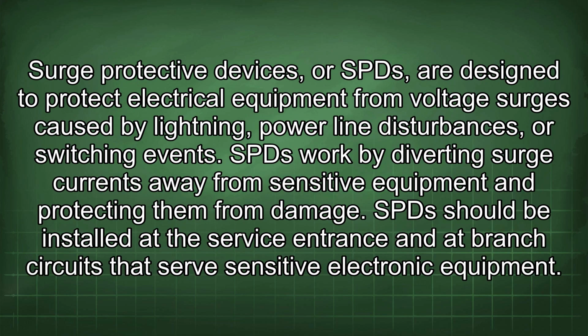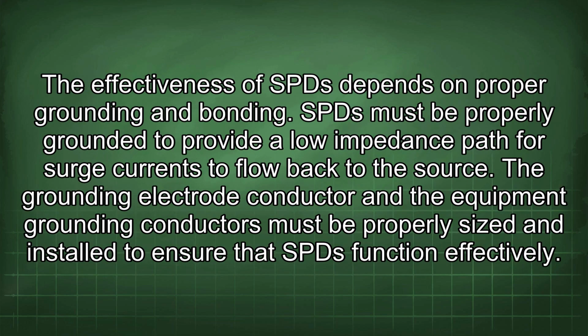Surge protective devices, or SPDs, are designed to protect electrical equipment from voltage surges caused by lightning, power line disturbances, or switching events. SPDs work by diverting surge currents away from sensitive equipment and protecting them from damage. SPDs should be installed at the service entrance and at branch circuits that serve sensitive electronic equipment. The effectiveness of SPDs depends on proper grounding and bonding. SPDs must be properly grounded to provide a low impedance path for surge currents to flow back to the source.